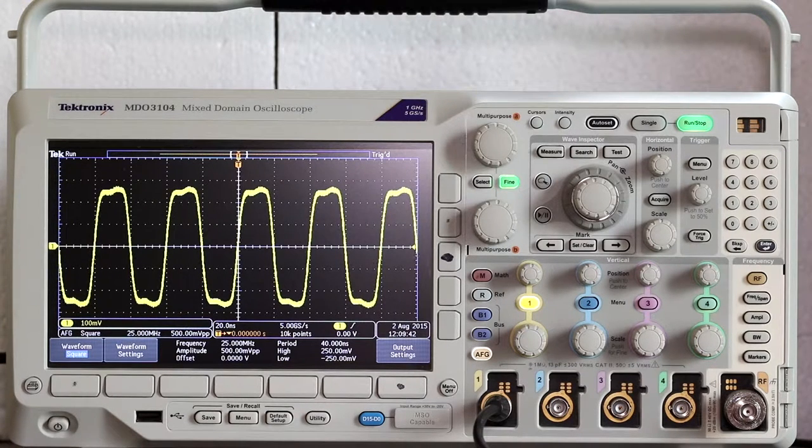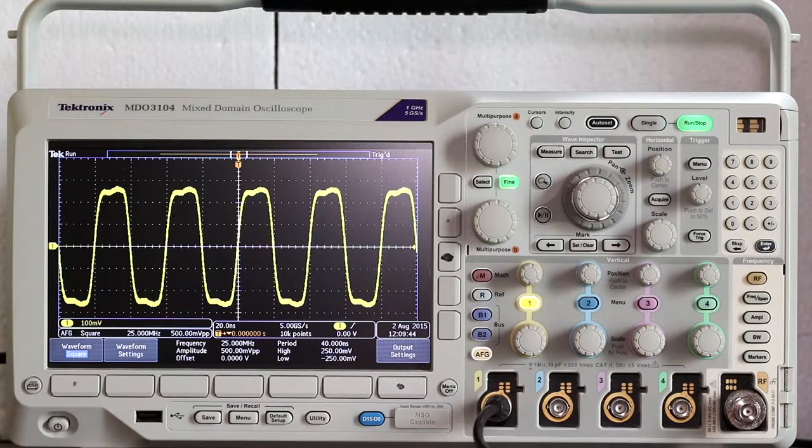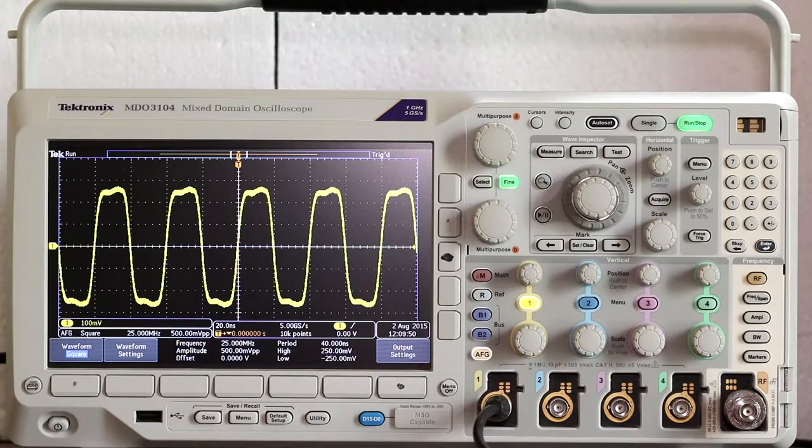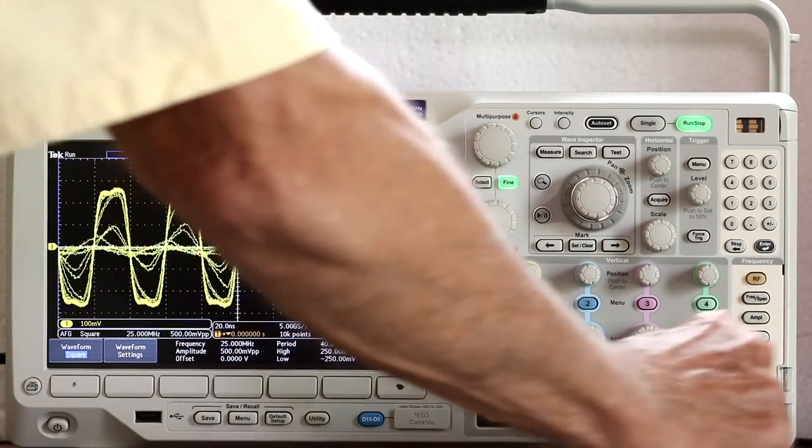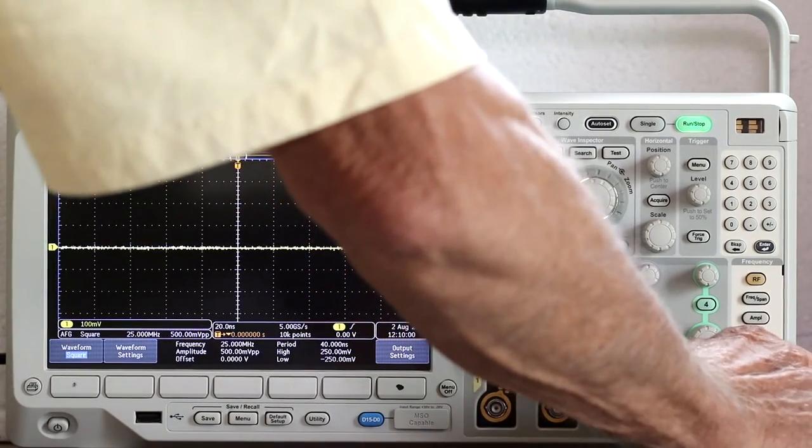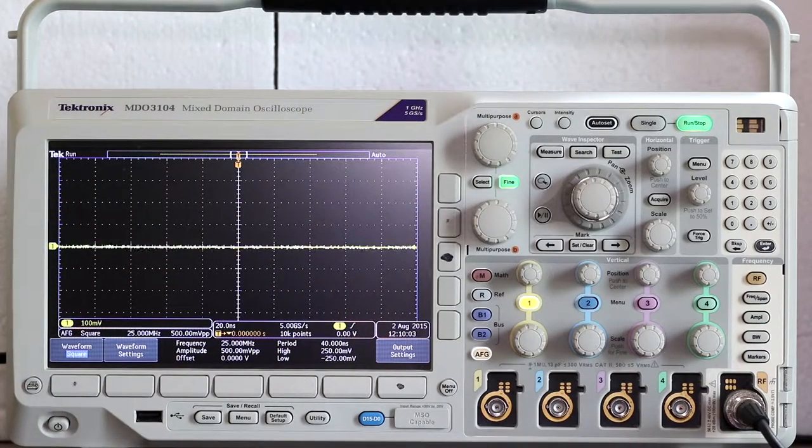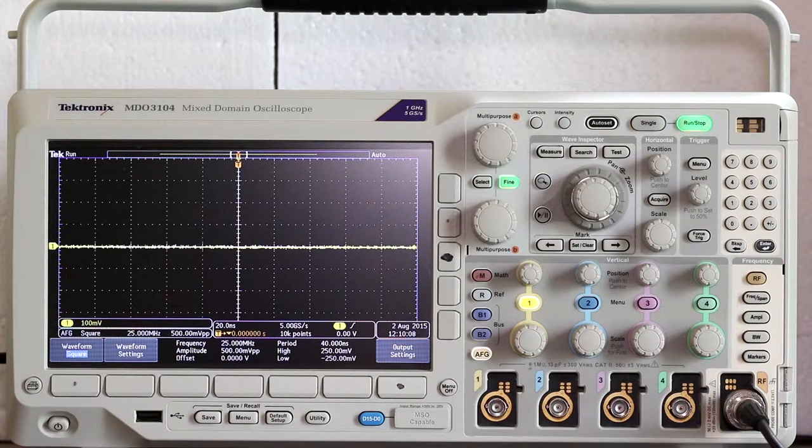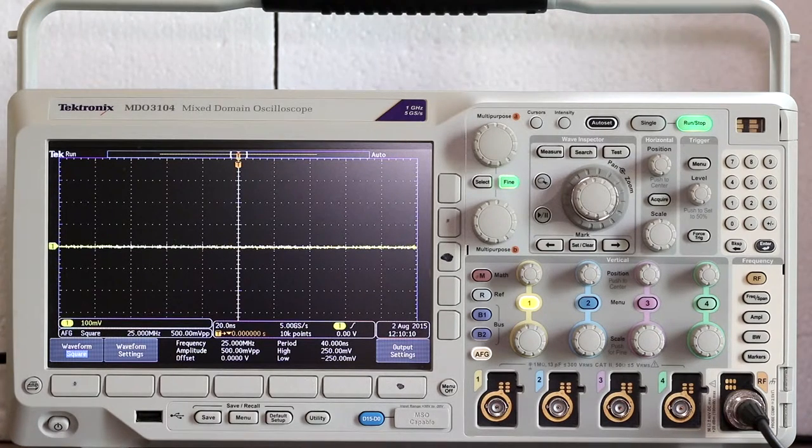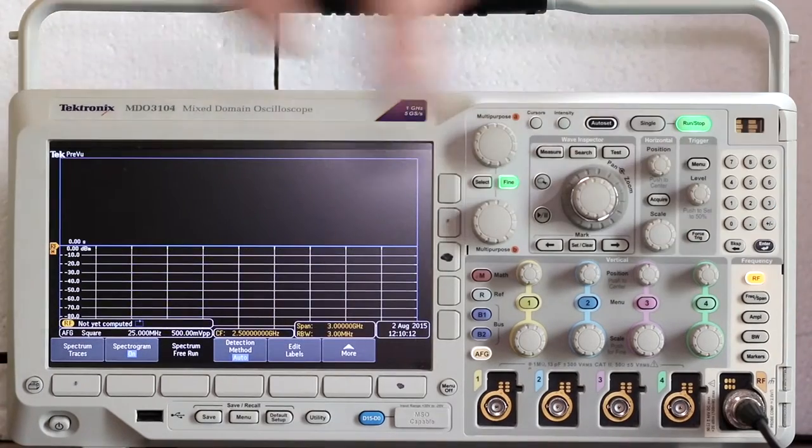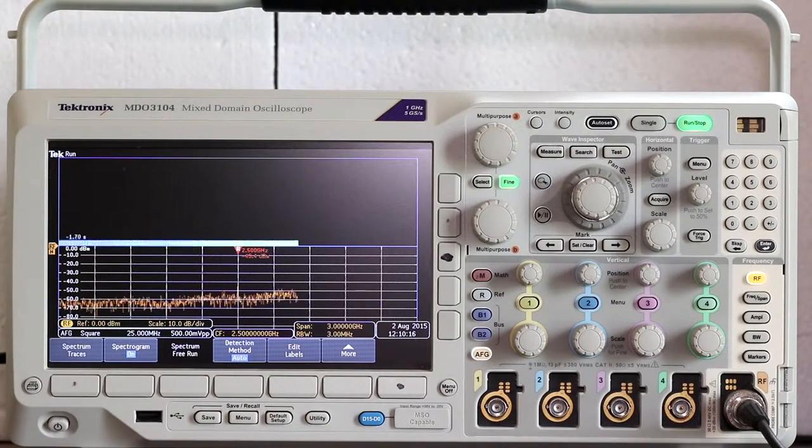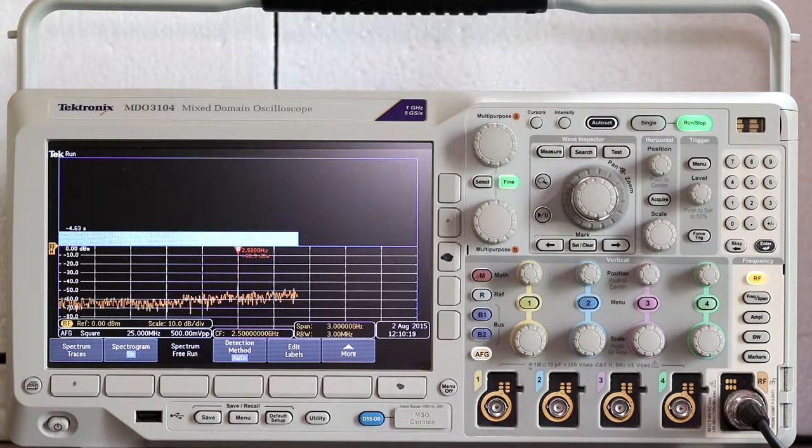Then, shift the AFG feed through the BNC cable over to the RF port, of course using the RF adapter. Press the RF button at the top of the column, directly above the RF port. Notice the AFG button remains lit, indicating that it is still active.